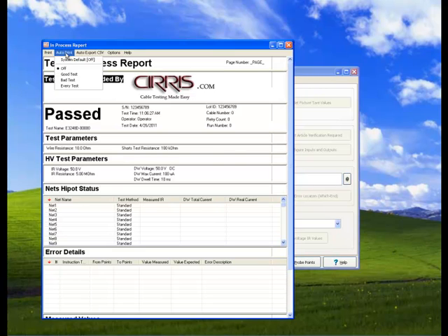Usually in the reports, an in-process report will print as soon as the screen turns good or bad, whereas a test report will only print once you remove the device and it's ready for the next device. That's the one that gets stored in the database, and is the next one we're going to go into, the test report. You can also set up some auto export to CSV.